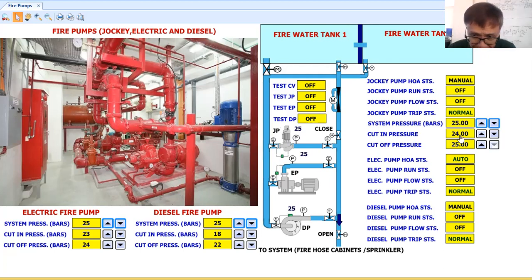Now here in my simulation, if the system pressure is 25 bars, and the system pressure drops 1 bar, so when the pressure is 24, then my jockey pump will cut in, or it will kick in. Okay. So that is the testing of this.